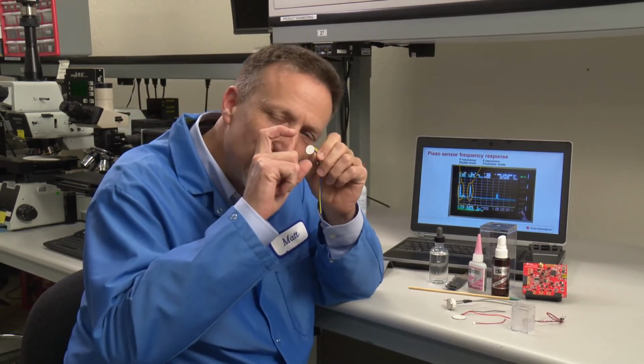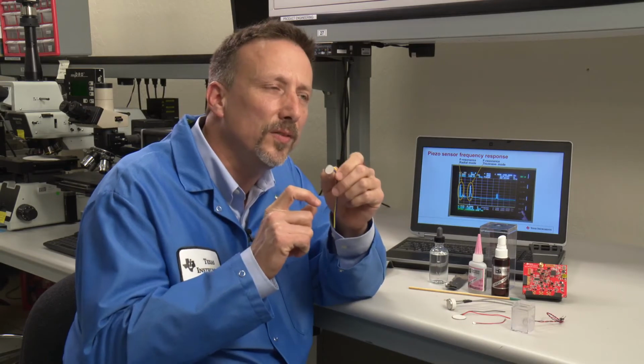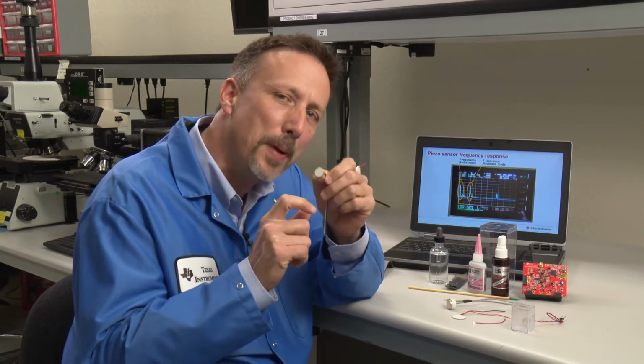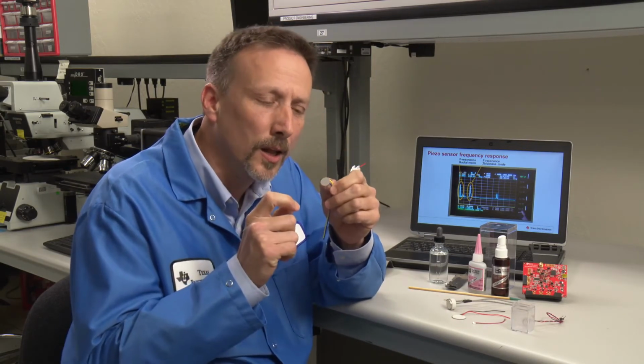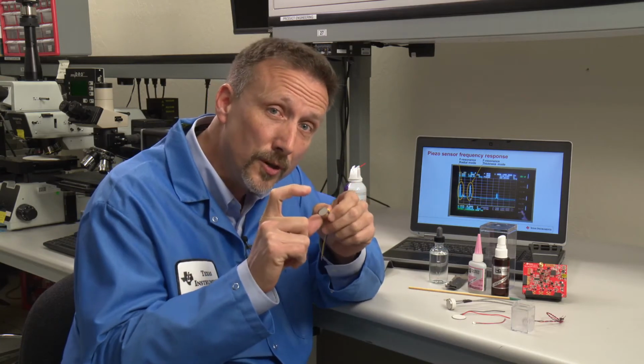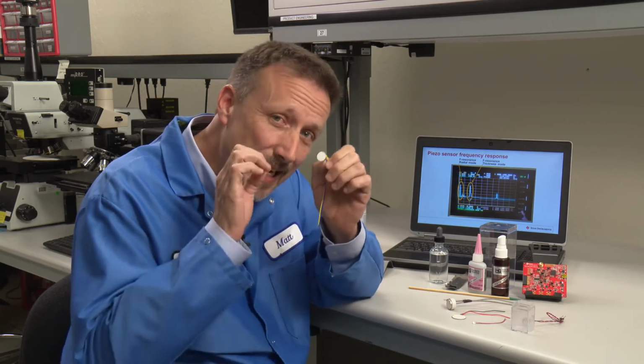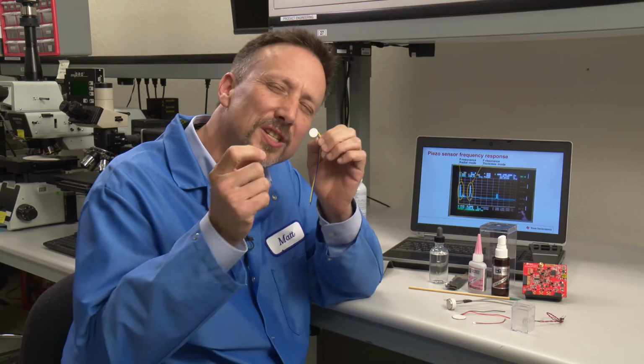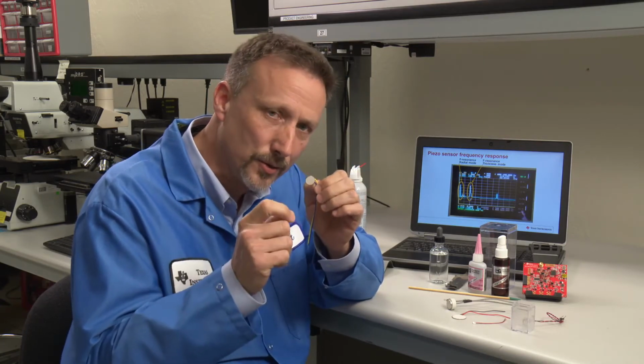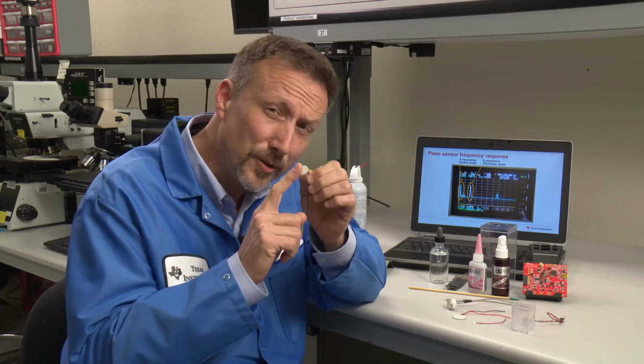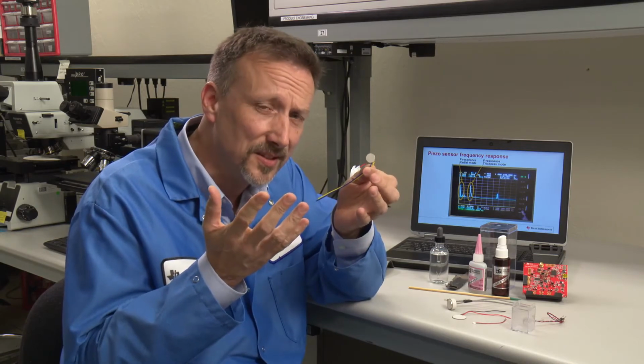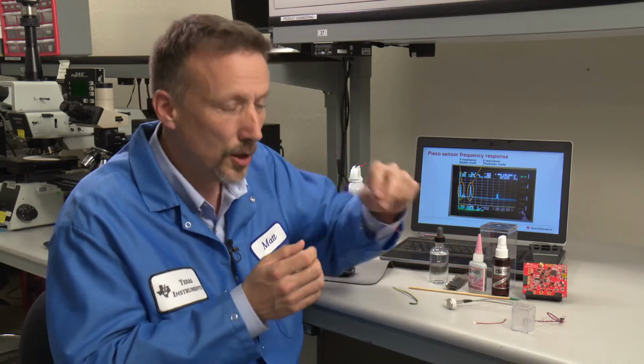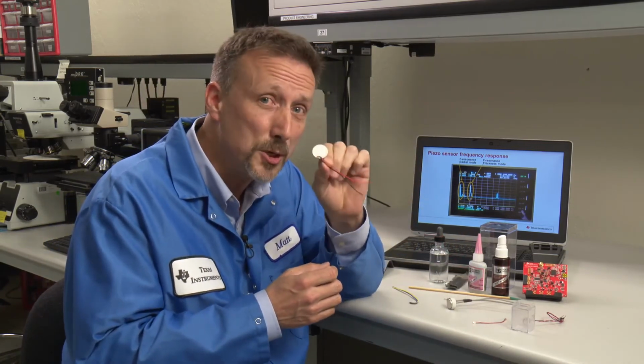The radius of the transducer is equivalent to its sensitivity and its power. In a nutshell, the larger the transducer, the more power it can send into your material and the more sensitive it is to those echoes. A medium-sized transducer has medium sensitivity. A larger transducer is much more sensitive.